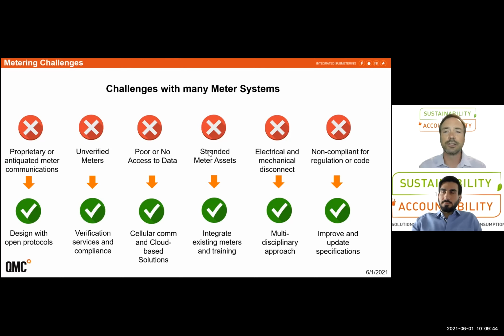So here are some challenges that we've come across in our history with metering systems. The first biggest challenge is proprietary meter hardware being deployed. So a manufacturer supplies and installs a system that really only they can read. And obviously that really limits the ability for the operations team or any other third parties to access that meter data and do good things with it. So our solution there is always deploy systems that have open protocols. Examples of BACnet, Modbus, TCP/IP, etc. are the way to design systems moving forward.